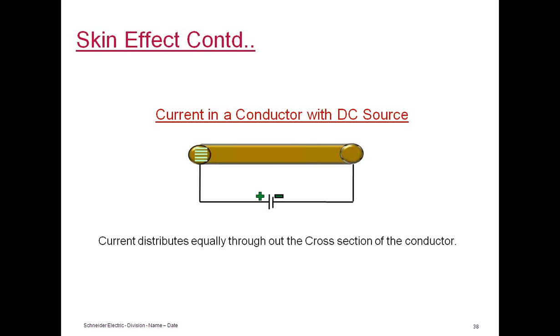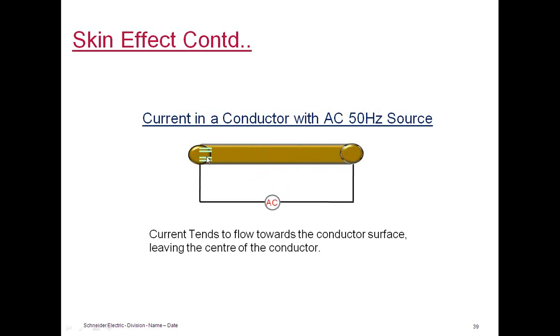So there is a phenomenon called skin effect. Let's say I have a copper conductor, a copper bus bar. We apply DC voltage to this, so electrons will flow across the conductor equally. Not even an atom is left out of the current flow. So electrons will flow equally across the conductor. If you apply 50 Hz or power frequency, the center part of the conductor is not being used to flow the current. That's because of self-inductance in the conductor. So this is called skin effect. The skin effect means the current will tend to flow toward the surface of the conductor.